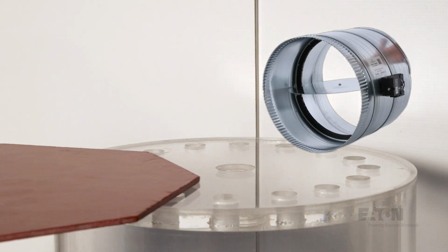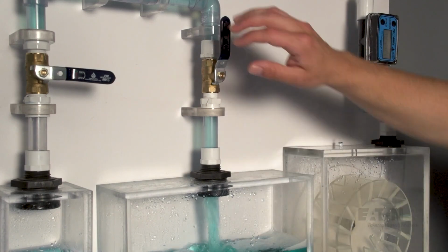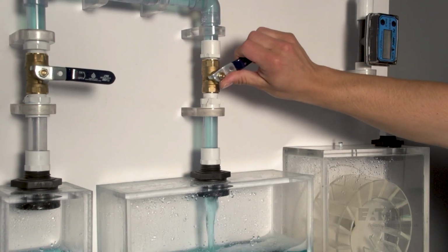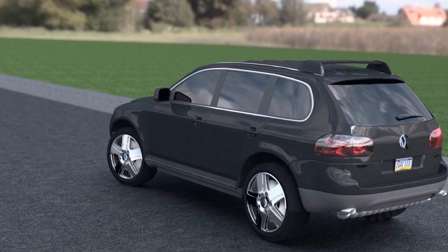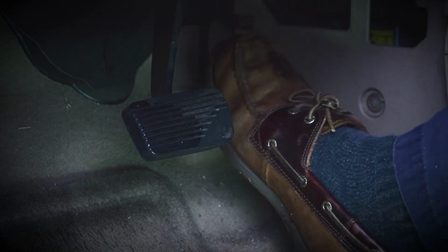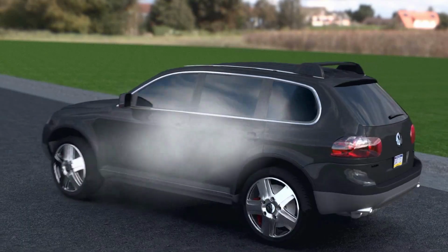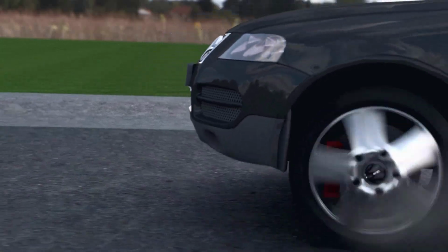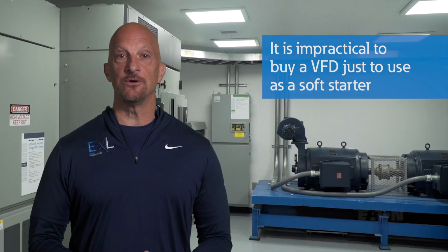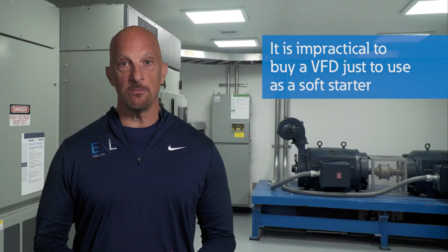If you use an across-the-line motor starter or soft starter, you would have to use dampers on an airflow system or valves on fluid systems to restrict the flow mechanically. From our vehicle example, this is like driving with your foot all the way to the floor on the gas pedal and controlling your speed with the brake. It's horribly inefficient.